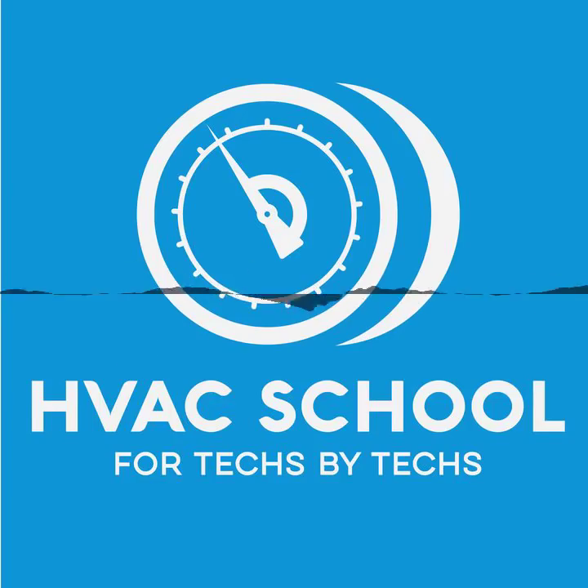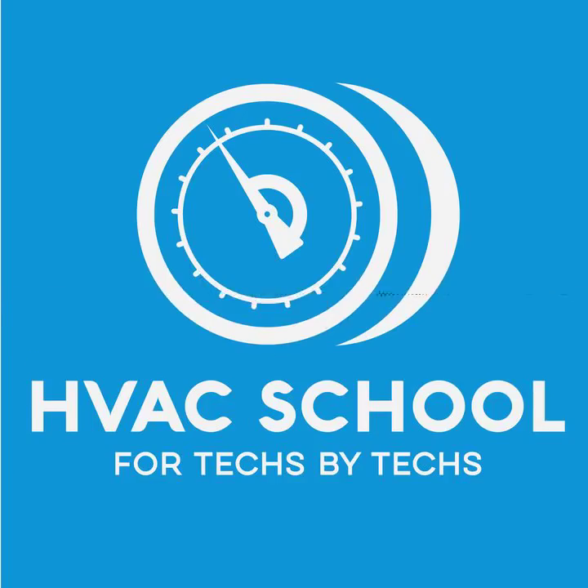So a lot of newer technicians will call me and say, "Hey, my contactor's not pulling in." All right, well, what are you reading at your contactor? "Well, I've got 24 volts." They'll say it just like that. I've learned over time not to trust that, because they'll say, "I've got 24 volts and it's not pulling in. What do you think it is?"